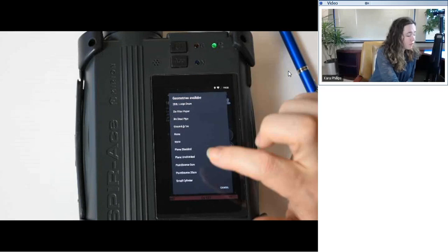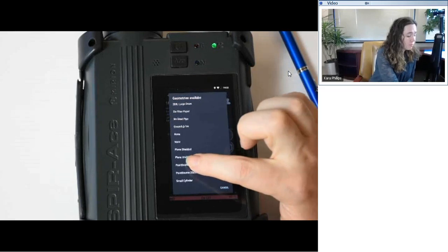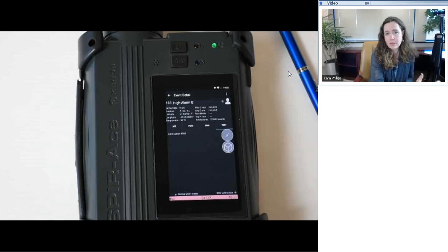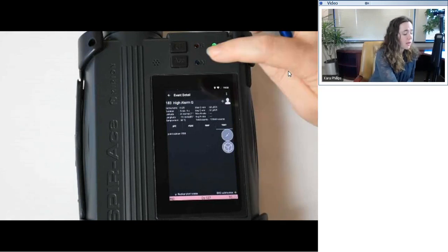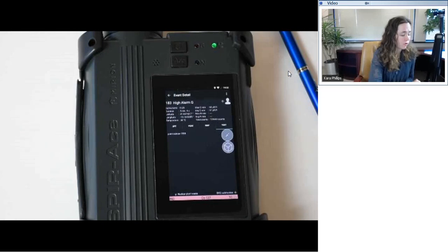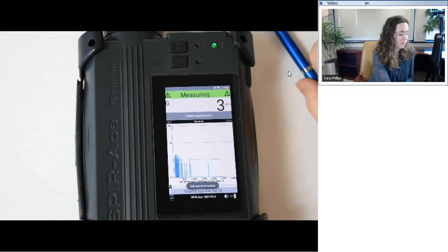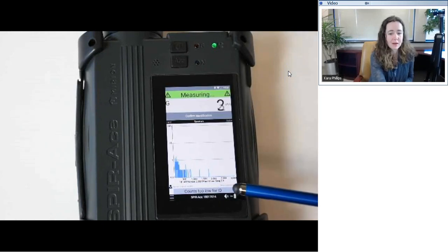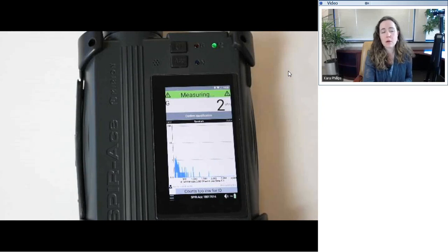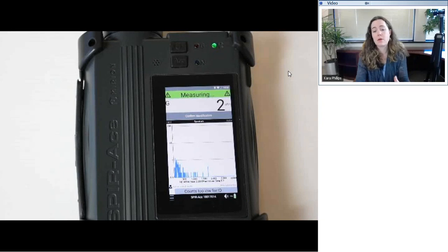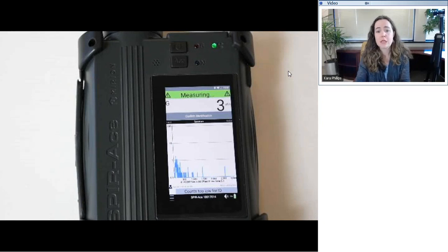It's a little bit tough to see here, but I'm going to take point source at 0 centimeters. That's pretty consistent with our geometry. I'm going to apply that. Then when I exit the screen, you'll see on the bottom here it says CAM conversion success. That means the GenieXport application has done its job: at the conclusion of the count, the SPIR-Ace app creates an N42 file, and then GenieXport takes that file and converts it to the Genie formatted CNF or CAM file.